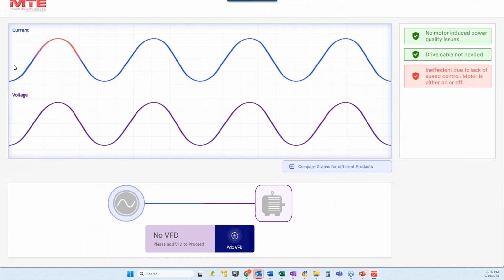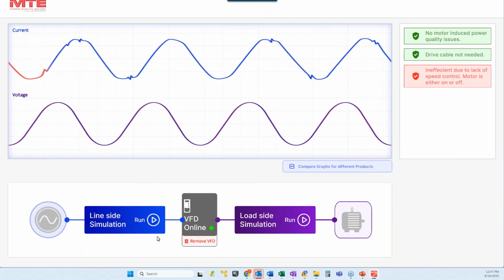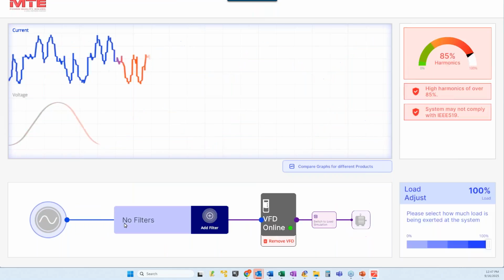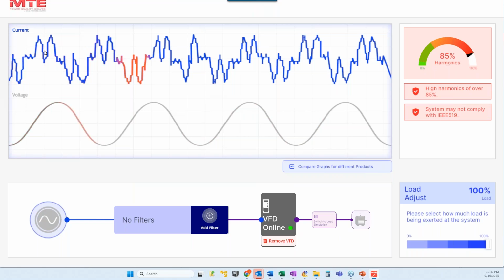And what's nice about this, here's your current, here's your voltage. If I have no VFD, as soon as I add a VFD to it, okay, you can see I'm getting notching on the current. And I can do a line side simulation. And so here's what the current's doing from the VFD that's feeding back into the system. So with no filters on there, this is what you got, okay?